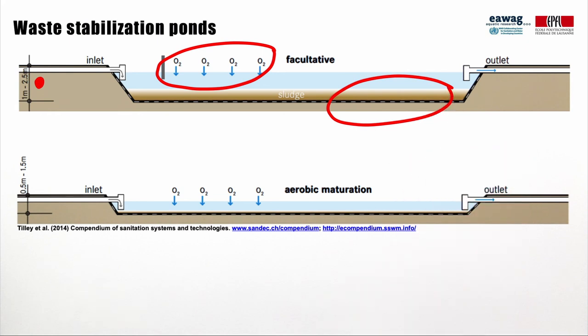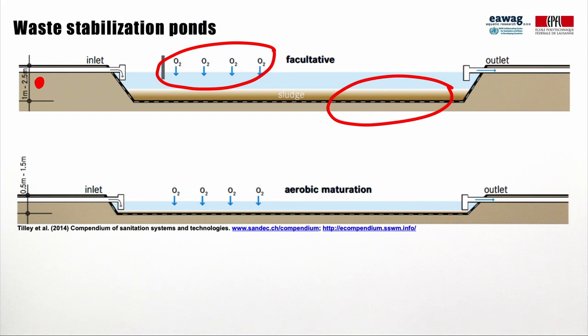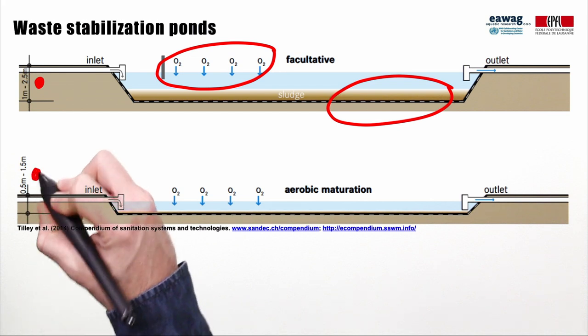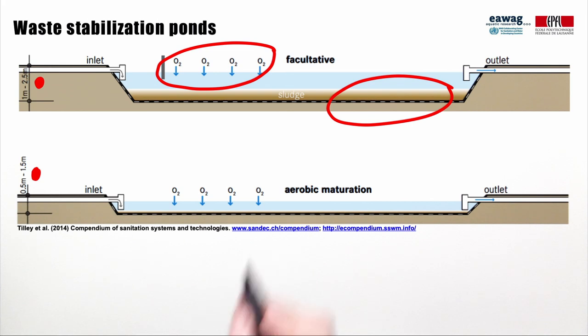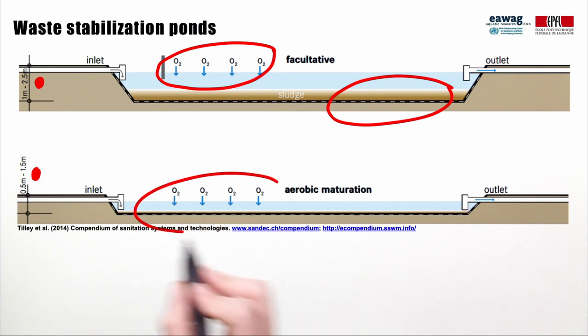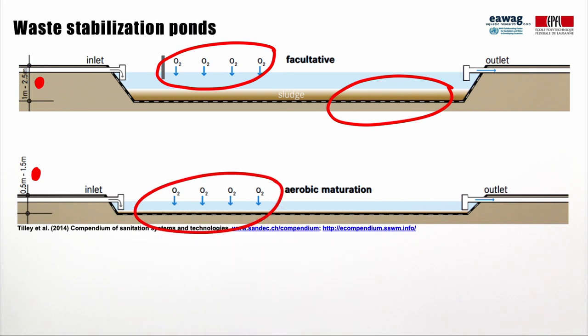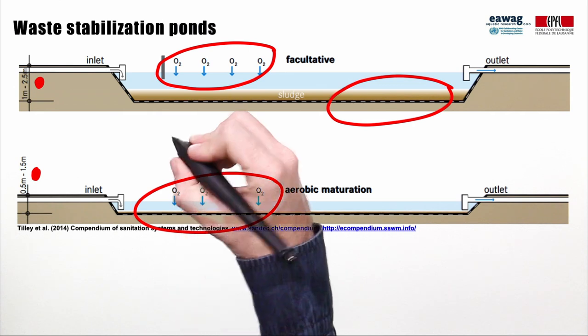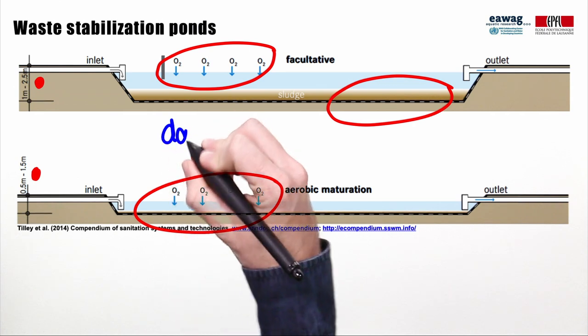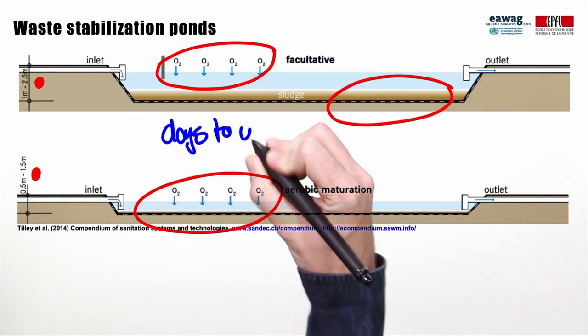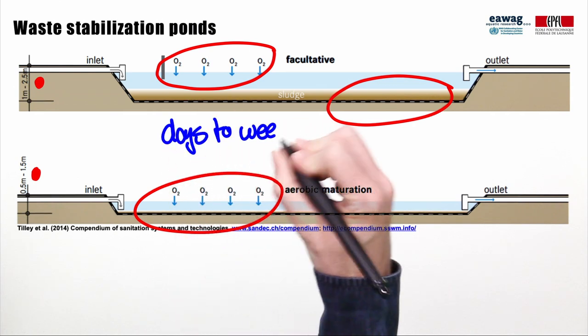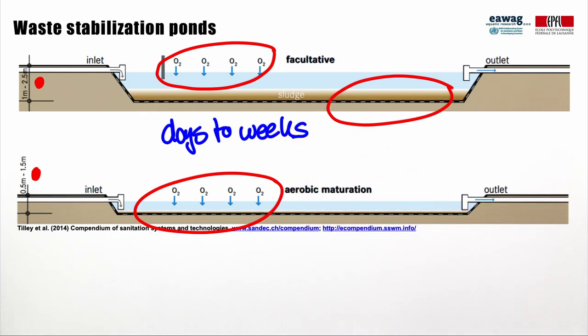At this stage, maturation ponds follow these facultative ponds. Maturation ponds usually have a depth of 0.5 to 1.5 meters, are aerobic, and are designed for inactivation of pathogens. The hydraulic retention time in these ponds is usually several days to weeks, which explains why they are land-intensive and require significant space.